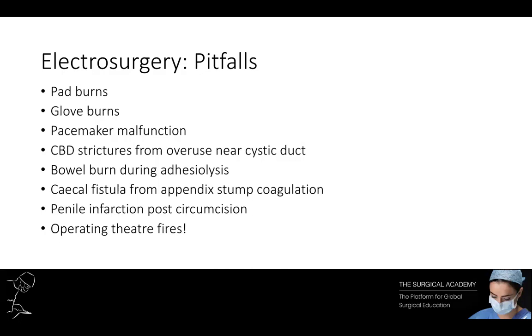Any current will take the path of least resistance, and implanted metal presents the lowest impedance path to an electrosurgical current. Therefore, placing a pad electrode on a leg with a hip prosthesis will encourage the circuit to pass through it. As the tip of the prosthesis has a small surface area, this could cause heating at that point. Similarly, metal jewellery can conduct stray current, resulting in contact burns especially between digits or to the leg — it should therefore be taped or removed. Body piercings in the current path should also be removed.